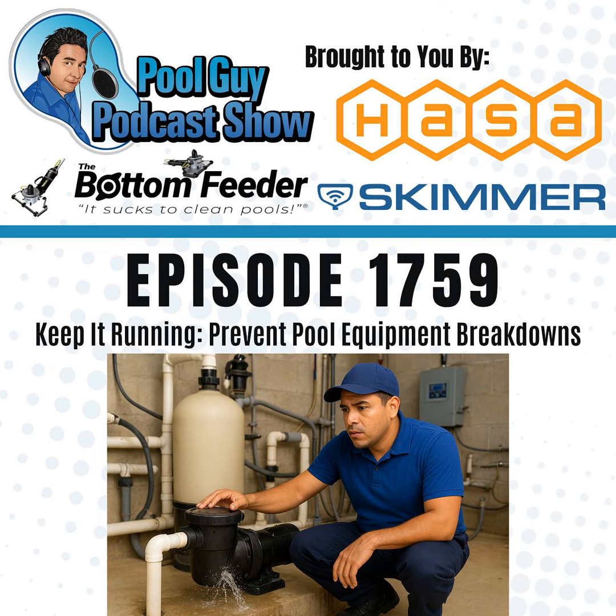You're also going to find that as the pump gets older, you may have a problem with the capacitor. The start or run capacitor is on top of the pumps usually. Those are the best pumps. There's some that are built into the back, which is a problem, but usually they're on the top of the pump. So you go to turn on the pump, you're going to hear it go and click off. So that's basically the capacitor. Those are easy to change, but I find that as the pump's getting older, they seem to go through capacitors a lot more, probably because they're getting older and the voltage spikes or whatever.